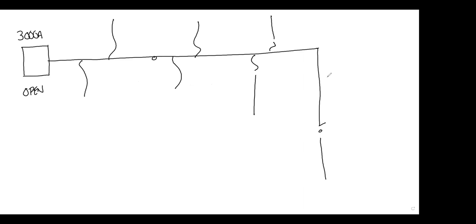So my understanding of load, and if I'm wrong, please correct me, is that unless there's something in the circuit to absorb that current... Now you're talking current, not load. Okay. So what do those lines represent again? Tap lines, fuses, all kinds of stuff down the street. Oh yeah, that's load. That's definitely load. With the breaker open, it's still load. That's still an existing load.